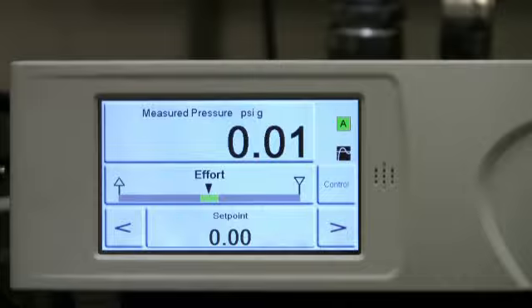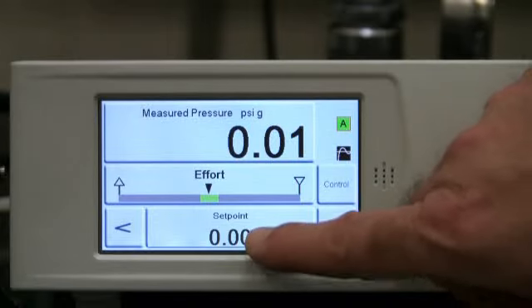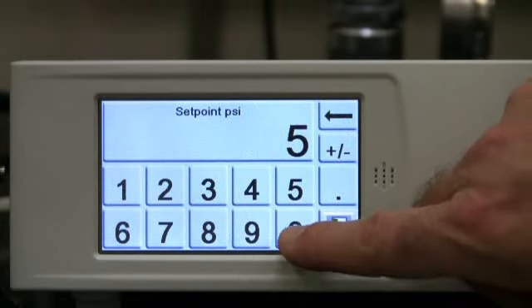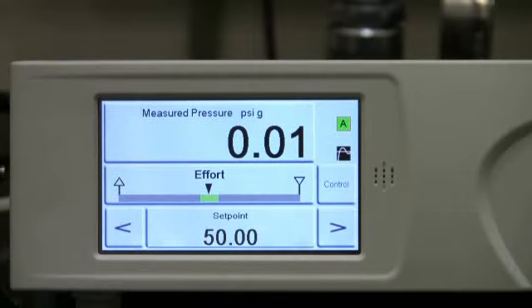PACE5000 provides immediate feedback to the user on the test conditions. We can also utilize the leak test function under the task menu, which we will see later. Either way, the choice is yours. Next, we will enter 50 psi as the first set point pressure using the numeric keypad, and then select Control to change the PACE5000 from measure mode to control mode.